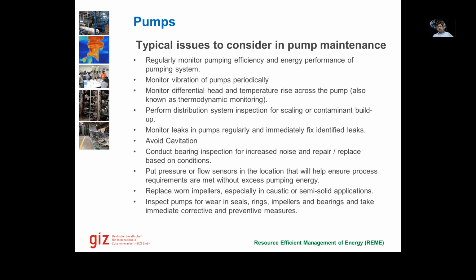We found out that the seal of a pump was leaking, and this pump was actually transmitting chemicals. The seal was leaking only drop by drop, but when we collected it and measured the time flow of this leakage, it amounted to hundreds of dollars per month, because it was chemical, not only water. So leakages are very much relevant in pump systems as well.